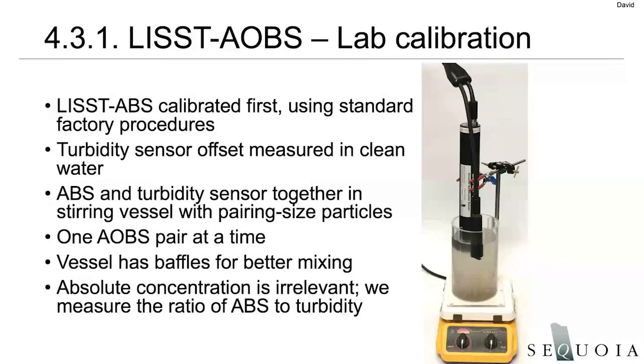It's fairly easy to judge whether the stirring is proper by changing the height, or the depth, I should say, of the sensors in the water. The ABS does not see the bottom of the tank until you get within 10 centimeters. So you can move this up and down a little bit in depth and see whether that's correlated to the readings. And if it is not, then you have achieved good mixing.